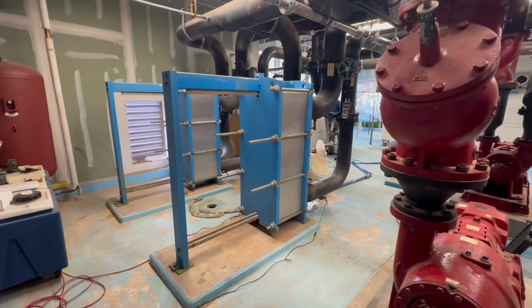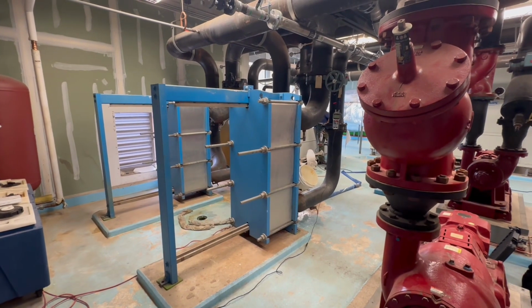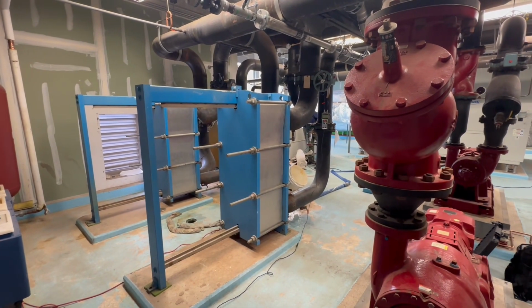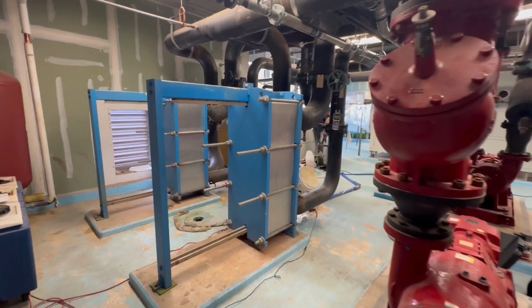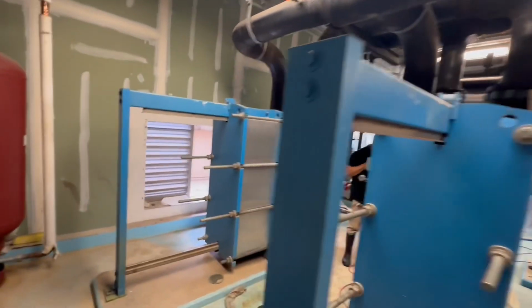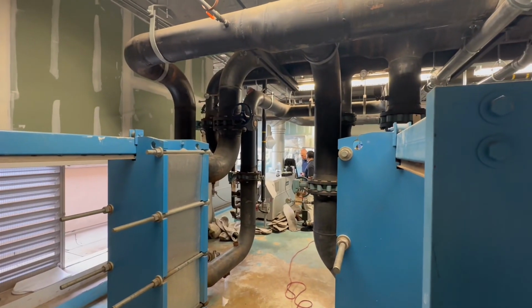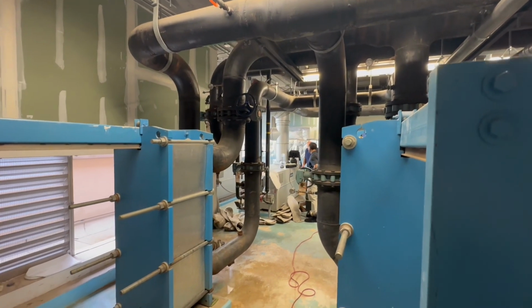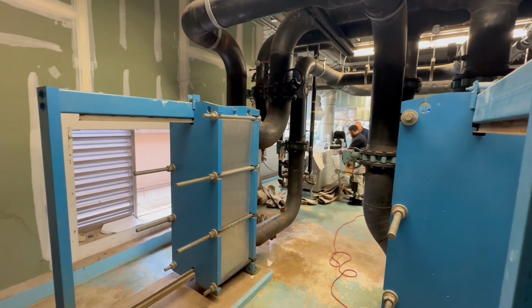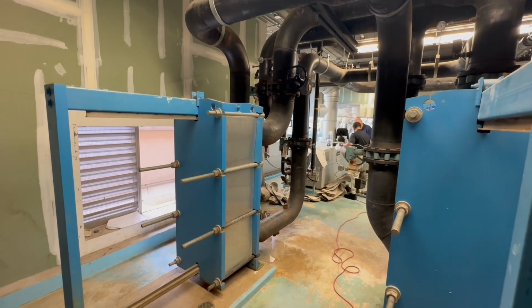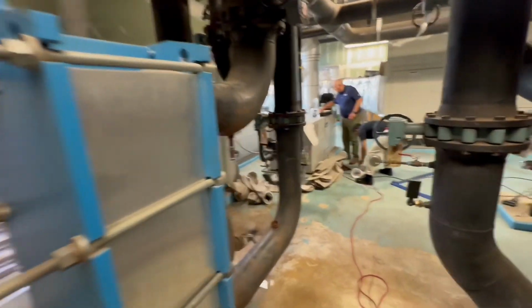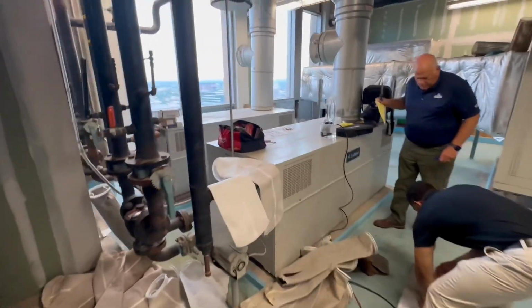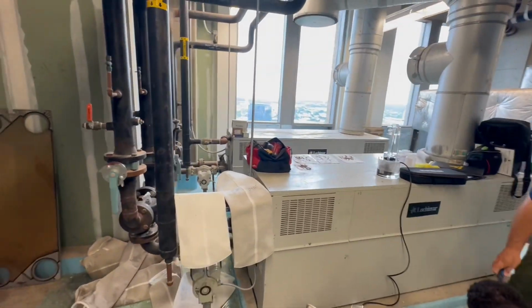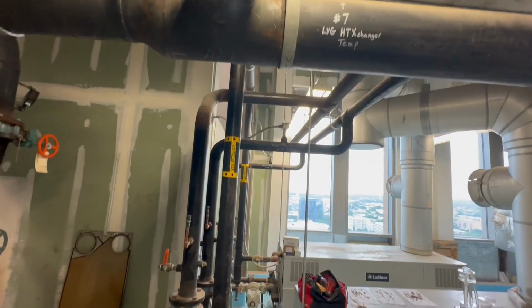So we don't actually have a chiller. We have a plate and frame heat exchanger, which separates the open loop cooling from the closed loop cooling. The closed loop cooling is on this side, and on the closed loop side, it circulates through heat pumps in residential units. They use these plate and frame heat exchangers to separate the cooling water from the closed loop system in the summer, and then in the wintertime, they have some boilers right here, Lochinvar boilers that separate the closed loop side from the open loop side.